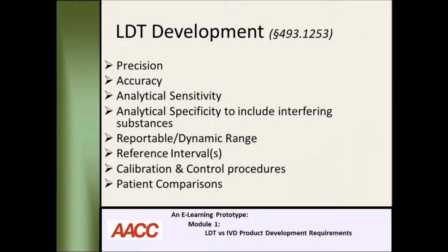So let's delve a little bit deeper into the similarities and differences between LDTs and IVDs. The list you see here are the analytical studies per CLIA that must be conducted prior to launching an LDT. The data generated are only a component of the entire process for launching an LDT, but they are the data that should be used as a reference for any future investigation, updates, and/or responses to inspectional inquiries.